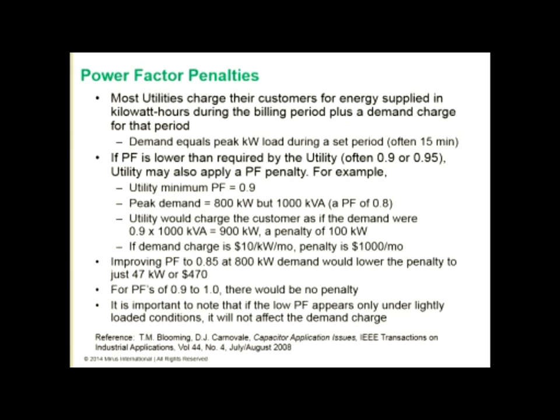The utility would charge the customer as if the demand were 0.9 times 1,000 kVA, so the power factor being 0.9, which would be 900 kilowatts, which would result in a penalty of 100 kilowatts. So if the demand charge was, say, $10 per kilowatt per month, that penalty would be $1,000 per month. So these penalties can be quite severe depending on how low the power factor is and what level the utility's minimum power factor is.